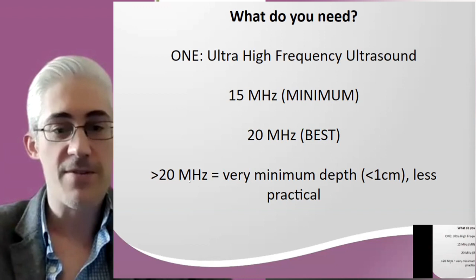So if you're interested in doing facial aesthetic ultrasound, this is what you need. You need a high frequency ultrasound that's a minimum of 15 megahertz. The best is 20 megahertz. When you get over 20 megahertz, the depth is so small, it's less than a centimeter penetration, that it really gets less practical for seeing things in the face. It's nice to have at least 3 centimeters of depth. That will get you everywhere you need to be on the face.